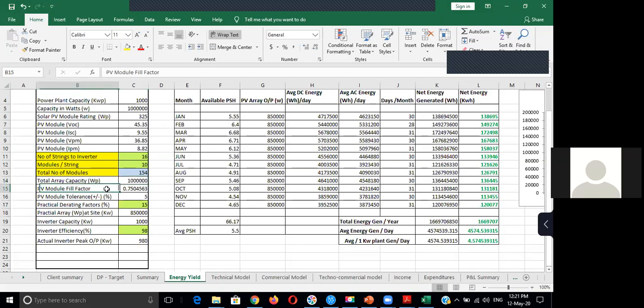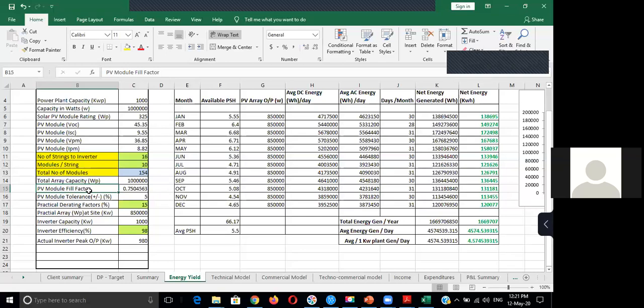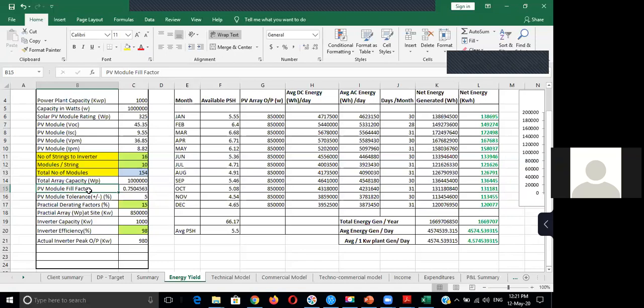And this is the module fill factor. Fill factor is nothing but the formula usually denoted as VMP×IMP divided by VOC×ISC, which is nothing but what is the practical maximum output you are getting divided by what is the ideal maximum output you are supposed to get. So if you do that calculation, then the factor you are getting is a PV module fill factor. This fill factor actually decides the kind of output you will get from the module. Let's say if you're having a hundred watt solar panel and your module is having a fill factor of 0.8, you will only experience maximum of 80 watts out of that module. And this fill factor and efficiency are both different parameters - efficiency denotes its performance, whereas the fill factor is its ability.